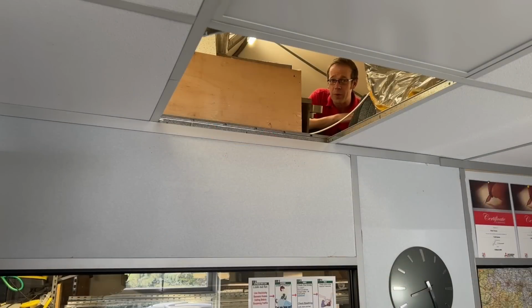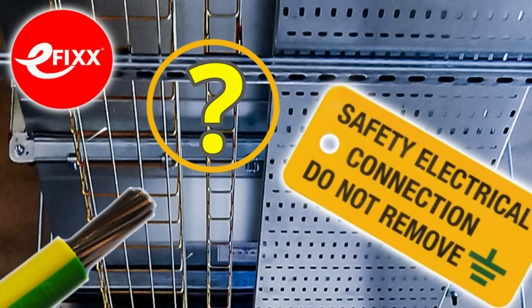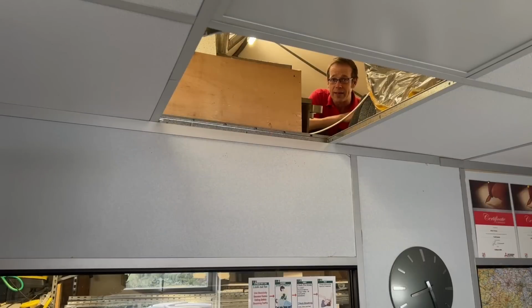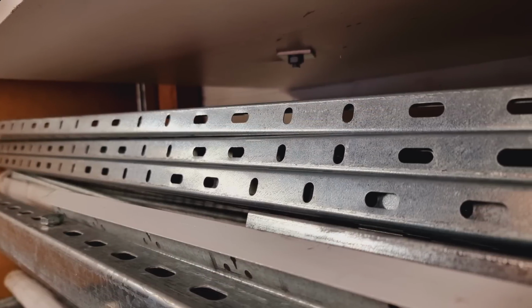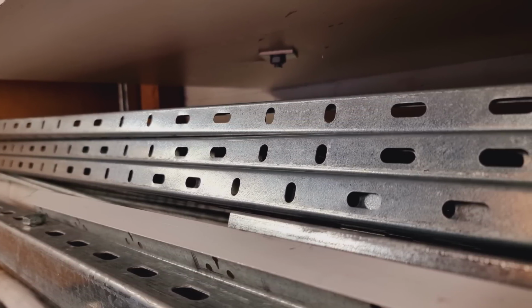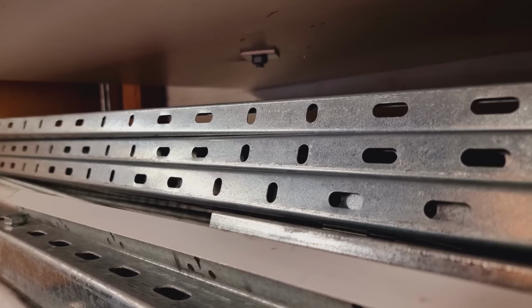Now, it's normally at this point in the video that people start to think, ah yes, but what about? For example, when I made the video pointing out that cable tray generally doesn't need bonding, there were various comments outlining situations in which it could become live and therefore should be bonded. I'll just give you one example. Now, this is really not to have a go at anyone's opinions or thought processes or anything like that, but someone outlined a situation where a forklift truck smacked into and dislodged some cables which dangled down and came to rest on a metal tray. So surely the tray being connected to earth would have been a good thing in that circumstance.